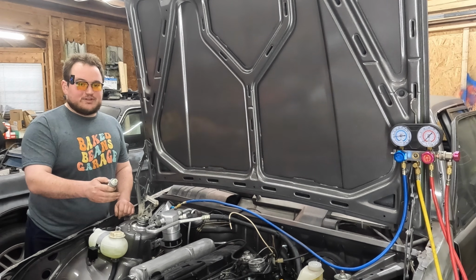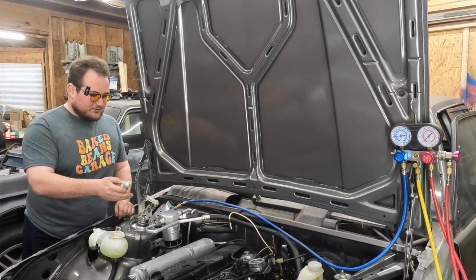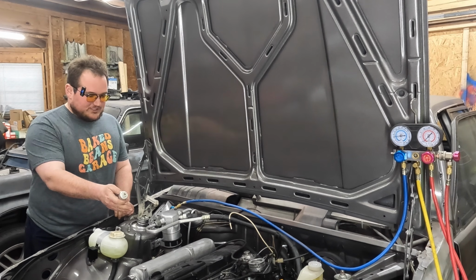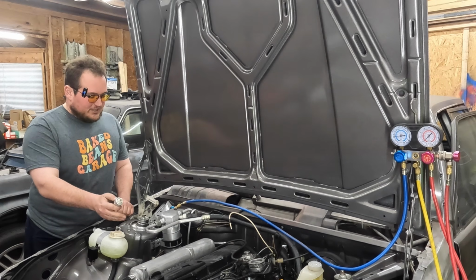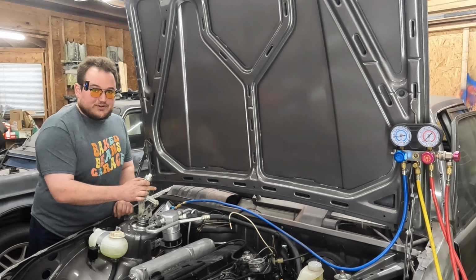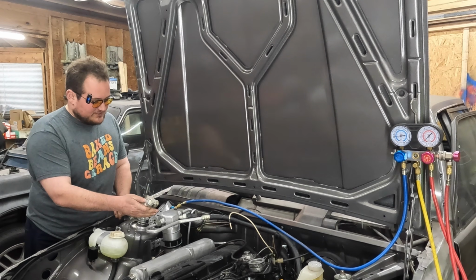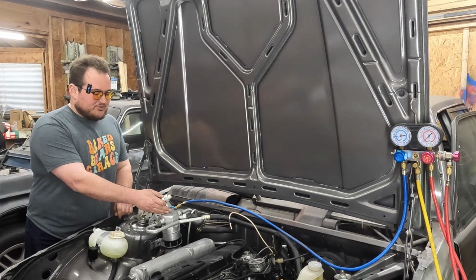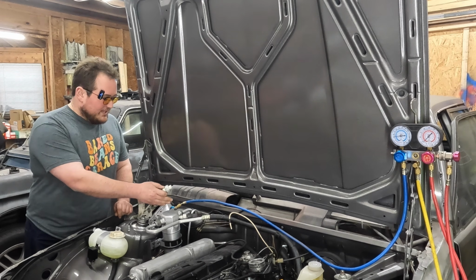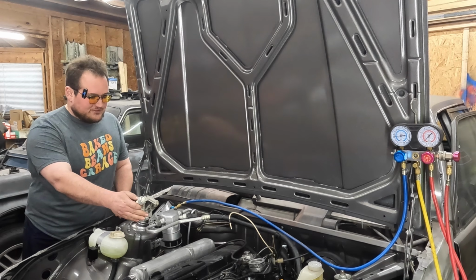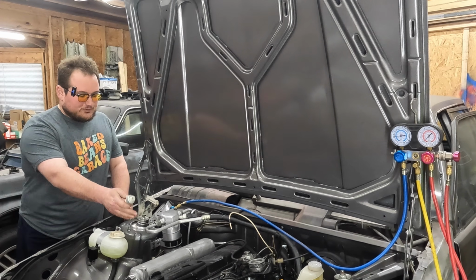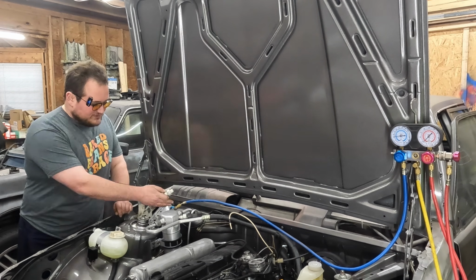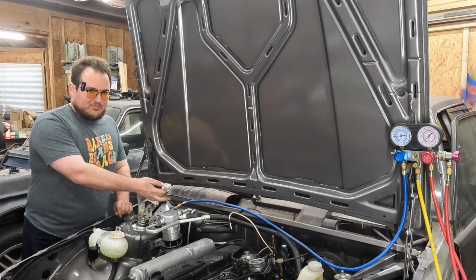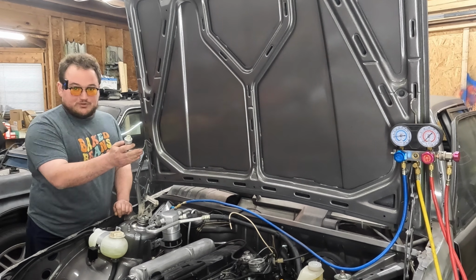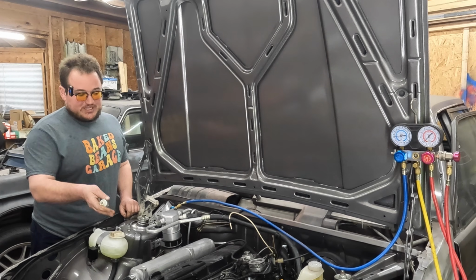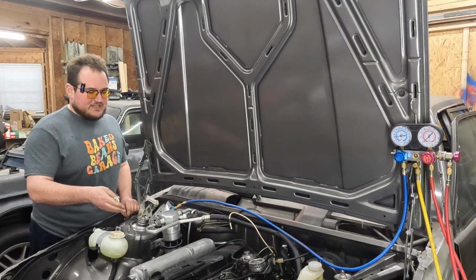So as we know, the higher the temperature of a vessel, the higher the pressure, the lower the temperature, the lower the pressure, and that's what it uses to control cycling the compressor on and off. So this switch is set to turn on at about 30 psi, and that's not just an arbitrary number. That is just the pressure and, by extension, the temperature at which the system knows it's getting dangerously close to start sucking up liquid refrigerant into the compressor, because once that gets so cold, it's not going to be able to evaporate, and you don't want to compress a liquid because it won't. Moving along to the high pressure switch, if there were one, that would just be a safety device.